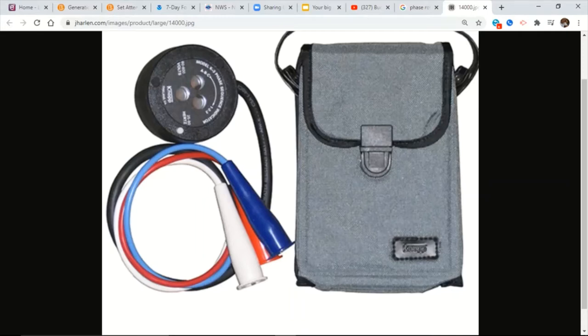If you don't do this and you go to replace a transformer, how many chances do you have? You've got three phases, so you've got a 33% chance of getting it right. If you don't get the phase rotation right and you energize a facility with three-phase motors, turning those motors backwards, you're pretty much going to burn up every piece of equipment inside that plant. That's not a good day.